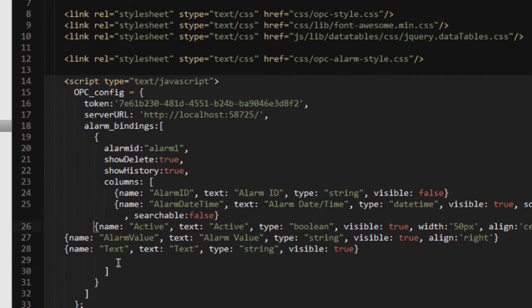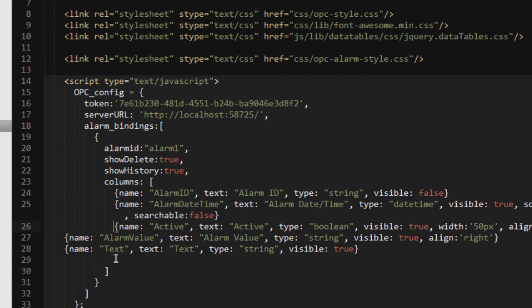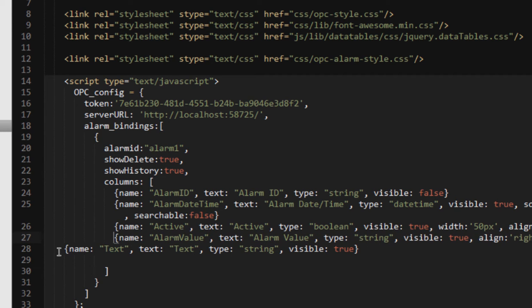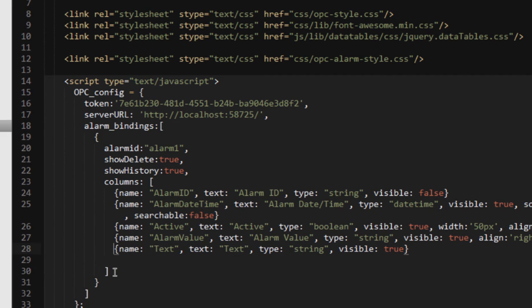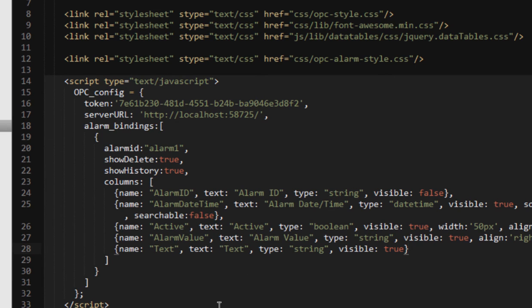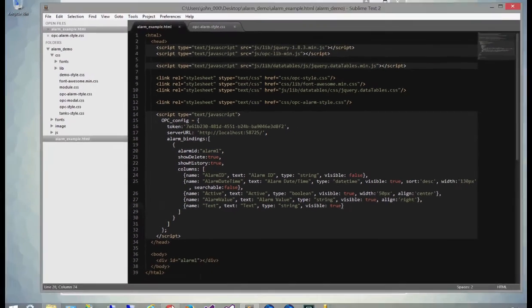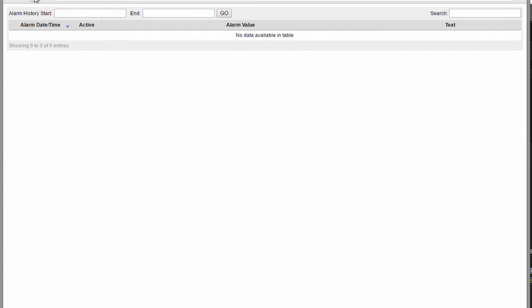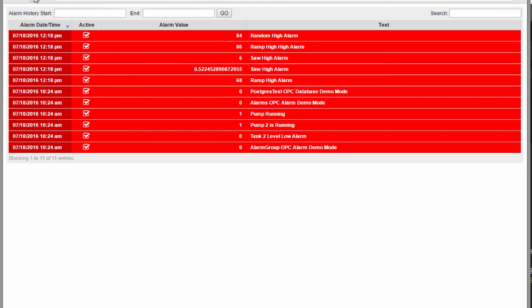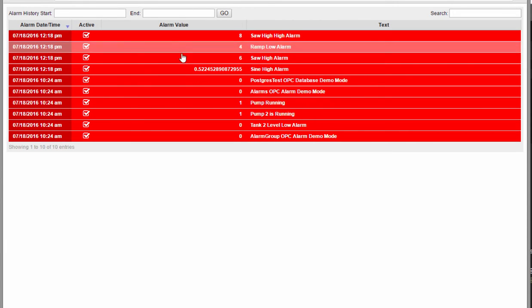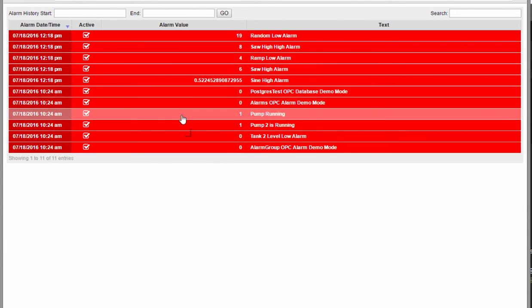And they display in the order that you put them in. So in this case, what I'm going to do is limit to the alarm ID, the alarm date and time, the active status, the value of the alarm, and the text. And you'll see in these attributes, there are things like visible, whether they show up on the grid or not, the width of them, the alignment, the text alignment, the type that's being displayed, and so on. So I'll refresh, and now you see that we've only got the date and time, the active flag, the value, and the text.